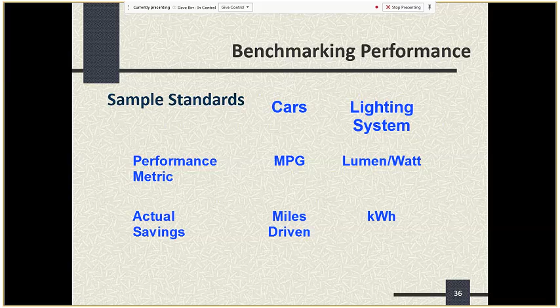Now, in baselines, you can look at a lot of different baseline types. You can look at a whole building, utility meter data. In the case of these facilities, you would be looking at a whole lot of utility meters because there are well over 100 in all these facilities. You start counting them all up. And it turns out that in large, complex, diverse buildings, you're better off looking at specific systems with measured and calculated data, or in some cases, like the PV system, sub-metered data. Because that just gives you a better way to define the actual baseline for a particular energy-consuming system in the building.